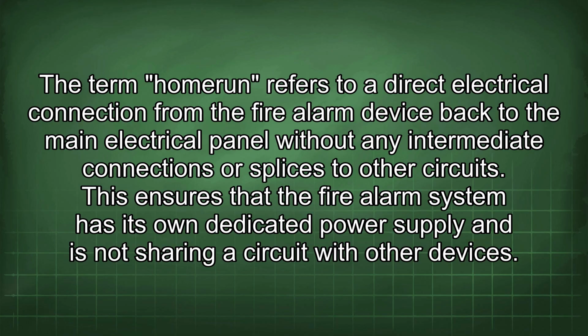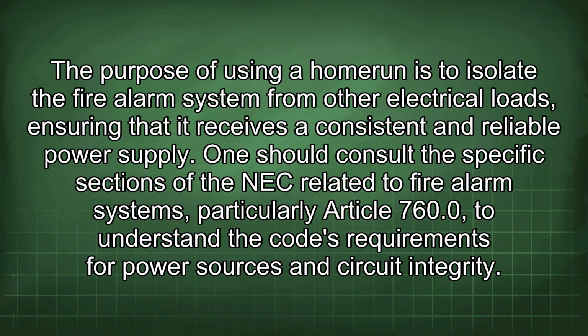The term homerun refers to a direct electrical connection from the fire alarm device back to the main electrical panel without any intermediate connections or splices to other circuits. This ensures that the fire alarm system has its own dedicated power supply and is not sharing a circuit with other devices. The purpose of using a homerun is to isolate the fire alarm system from other electrical loads, ensuring that it receives a consistent and reliable power supply.